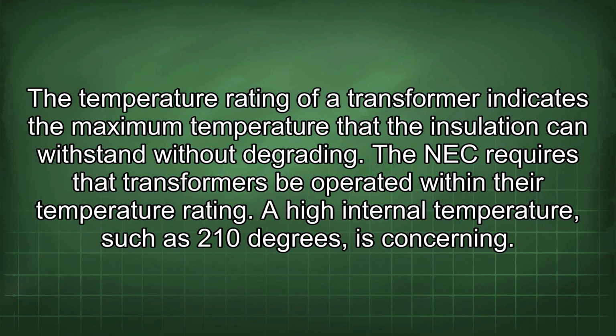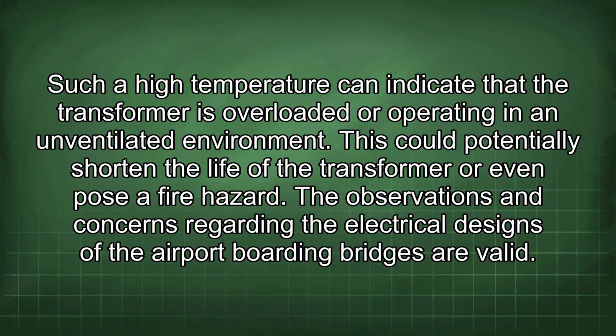Temperature rating of a transformer indicates the maximum temperature that the insulation can withstand without degrading. The NEC requires that transformers be operated within their temperature rating. A high internal temperature, such as 210 degrees, is concerning. Such a high temperature can indicate that the transformer is overloaded or operating in an unventilated environment. This could potentially shorten the life of the transformer or even pose a fire hazard.